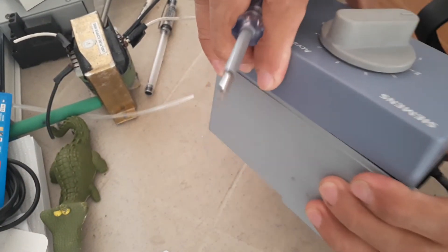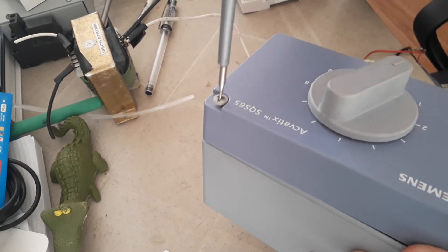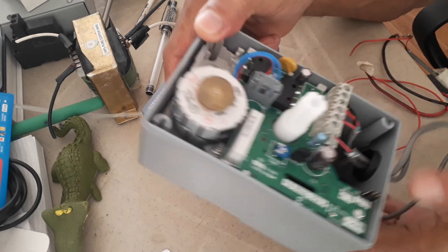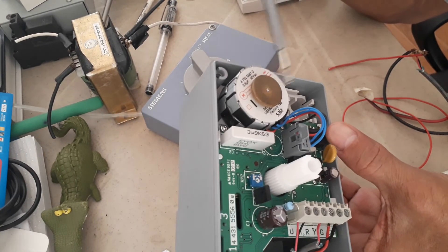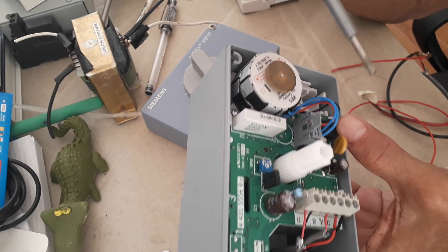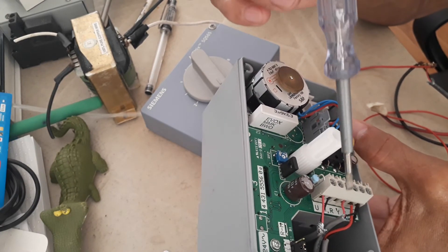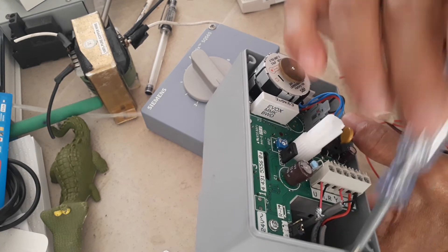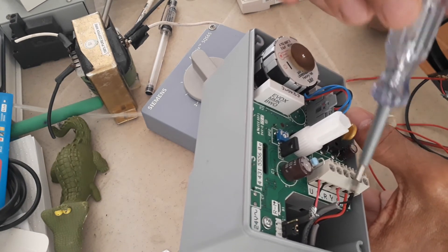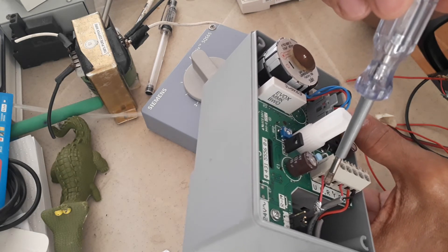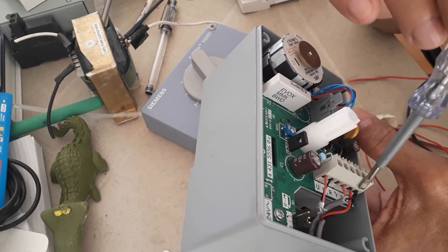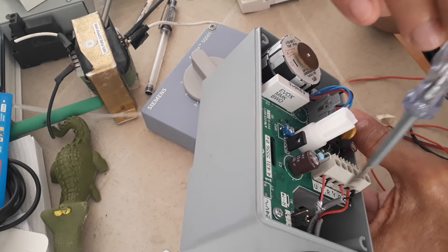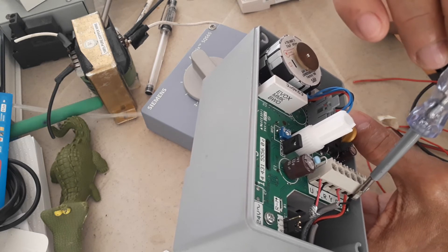Let me open this so we can see what are the things inside this valve actuator. As you can see here, this is the motor. Then, these are the terminals. As a BMS engineer, you will try to pull at least three cables. This is how are you going to terminate. This is for the feedback status, U and M. Then, Y is the control signal. Then, it is sharing the 24 volts. G and G-O, this is the 24 volts live and this is the common. As a BMS engineer, you should always pay attention to the details.